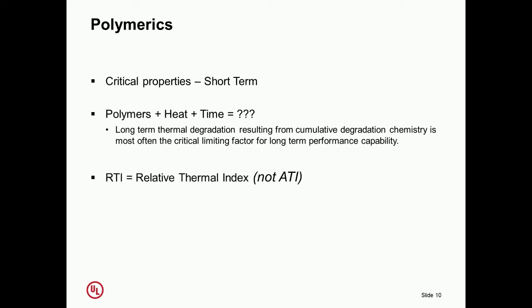If we look at general requirements for insulation coordination in the industries globally, we'd be looking at IEC 60664 and three different parts of that document. In the US the sister document is UL 840. That's where all requirements are established. We look at different features of polymers used as insulators in order to show their reliability. We work at short-term type properties, are concerned about heat degradation of polymers, but have to keep an eye open to the fact that some degradation mechanisms are changing as different implementations of polymers and systems are being used. Long-term thermal degradation has been one of the major drivers, the critical paths towards degradation of polymers.